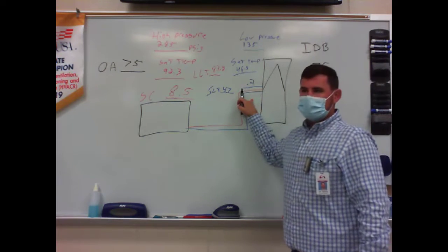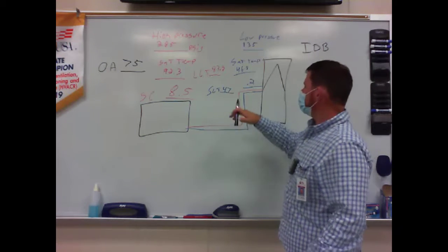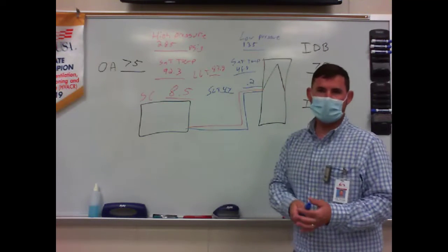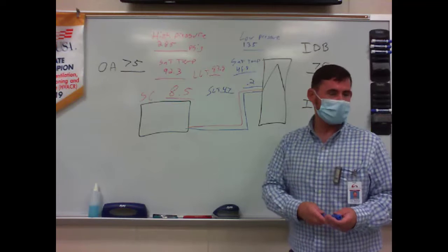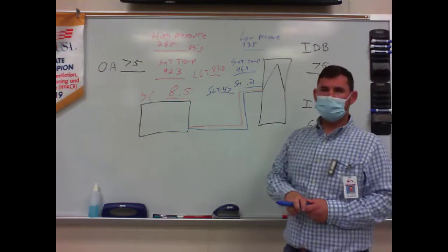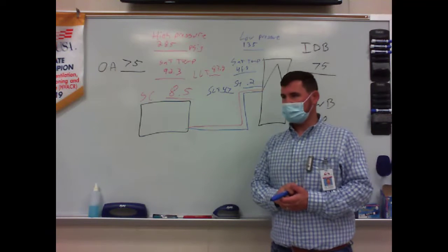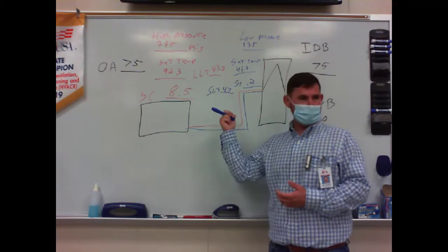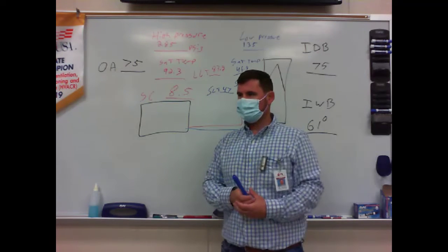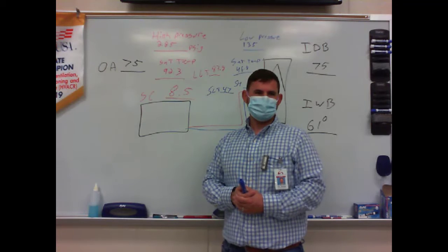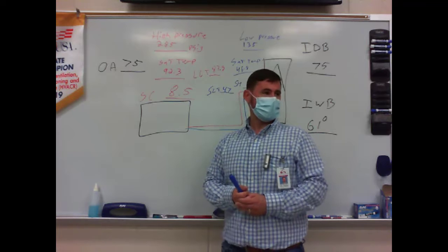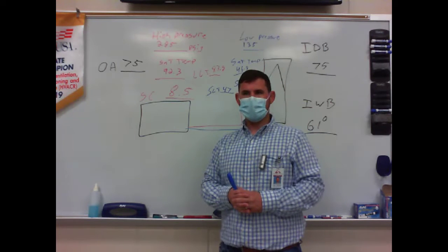So me looking at this system, when I look at superheat, it tells me whether my evaporator has the right amount of refrigerant, too much, or too little refrigerant in it. So with a superheat of 0.2, that tells me I'm completely flooded inside of my evaporator. I have too much refrigerant going in. What about my subcooling of 8.5? Does that look okay? It's okay. It's a little bit low, but it's okay.